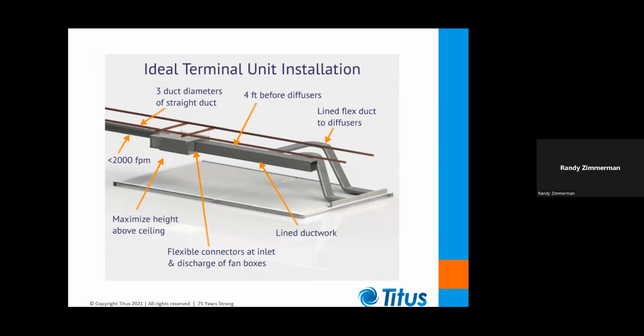Now, here are some pointers for ideal terminal unit installation. First off, we want to size our inlet duct for no more than 2,000 feet per minute. It would be a good idea to have at least 3 equivalent duct diameters of straight duct approach, although we say that we can deliver catalog performance with our boxes and our inlet sensors with only 1.5 equivalent duct diameters of straight approach. Then we want to put the box as high above the ceiling as possible, and we want to have a ceiling if at all possible, because a ceiling helps to block quite a bit of noise.